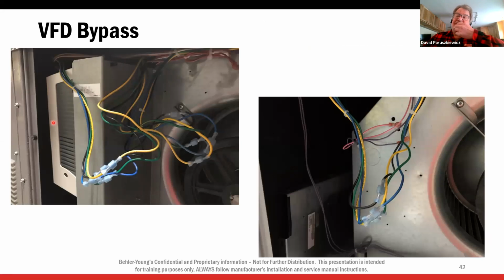All right, so here's a picture of the drive tucked away behind the unit or inside the unit. In the event you lose a VFD, right? So you're checking, I have line voltage in. I have a call on yellow for blower, right? So it's closed from pink to yellow. I've got a call. The blower's not running. So I check, I have my 230 input voltage. I have no output voltage. So I determine the drive is bad.